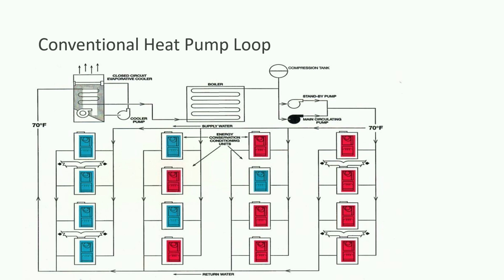So here's a conventional heat pump loop. This is what we've been doing for 25 years until we realized geothermal in New York is a possibility. The graphic shows a closed circuit evaporative cooling tower. Could be an open cooling tower and a boiler, right? So this graphic is showing generally, as long as I'm seeing 70 degrees, somewhere between 60 and 90 year round, I can get simultaneous cooling and heating.